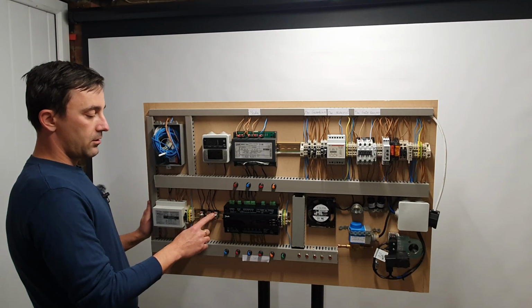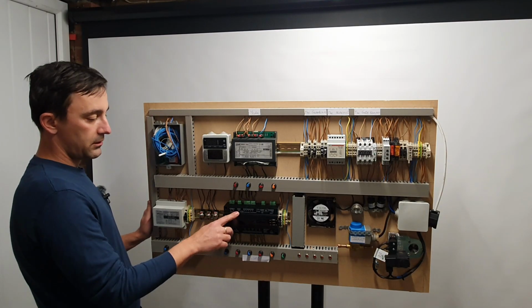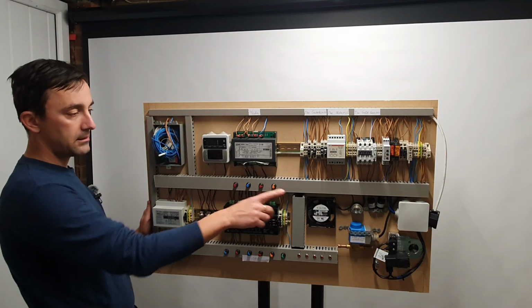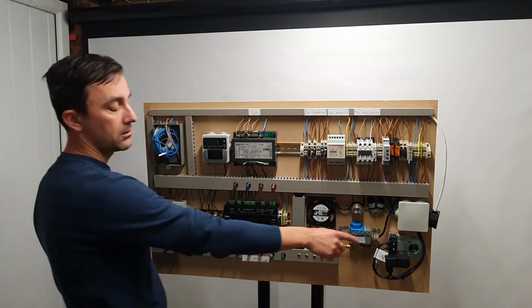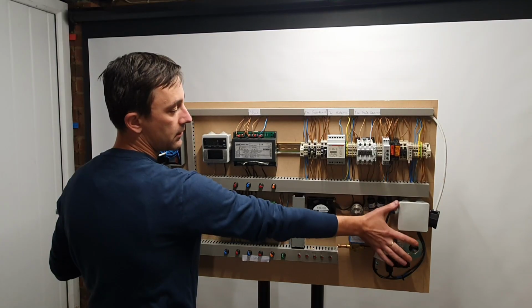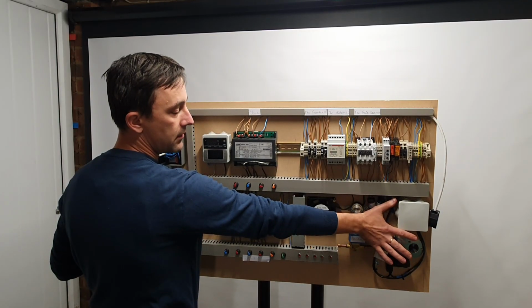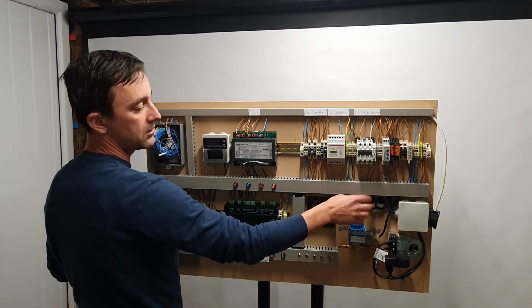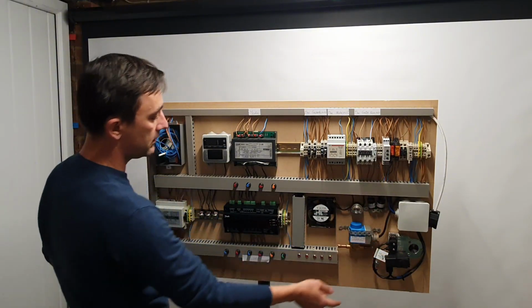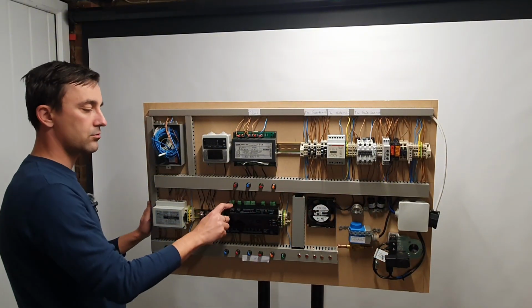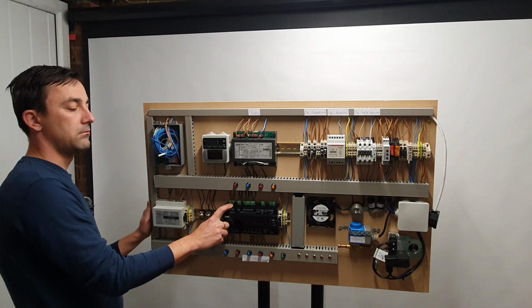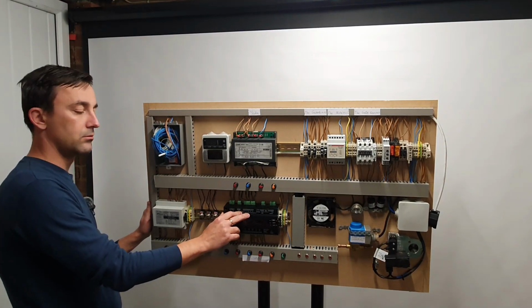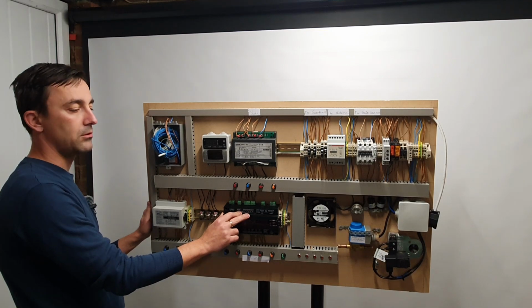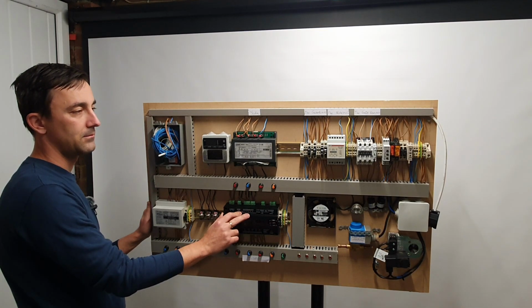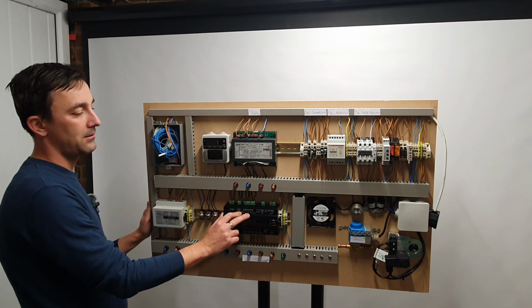This switch is our door switch for this controller, and this safety circuit switch comes back from our daisy chain safety components, Klixon, HP, LP. So if there's a break in this circuit, it would feed back to the controller and it would give the necessary information to basically stop the unit or display an alarm. So yeah, that's the panel.